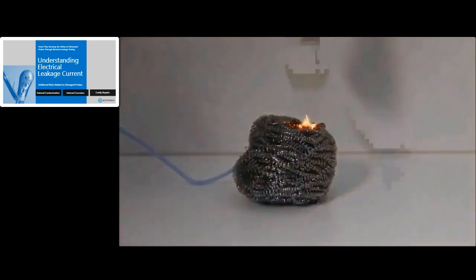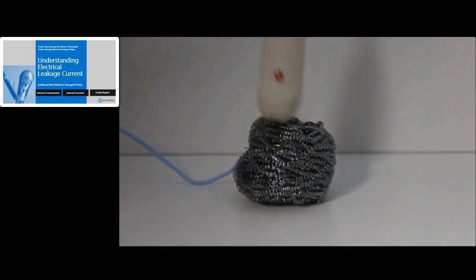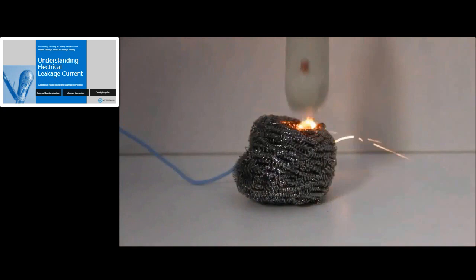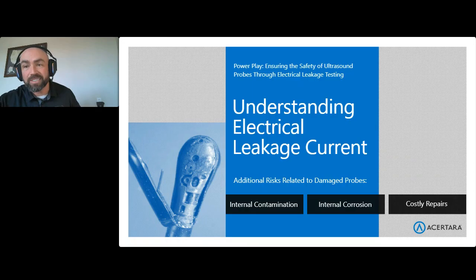So this is showing the danger of electrical leakage. This is a cardiac probe, and the insulator has been broken down intentionally here. Now you can see the amount of energy that's actually going through that probe can be significant and can be damaging. Usually it's not going to be that spectacular, but it can be life-threatening nonetheless. It's not good to have that happening.